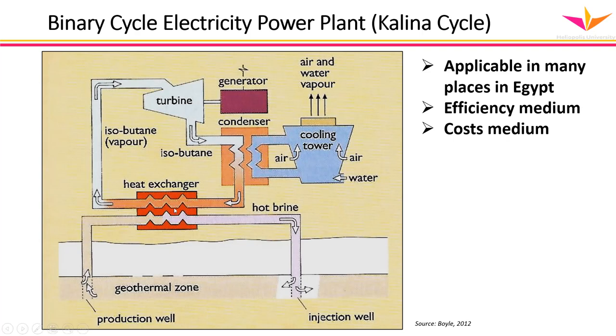Here is another picture of it. Hot water comes out, heat exchanger here in red, it boils the isobutane in this case, and that makes isobutane vapor. It drives the turbine, drives the generator, which makes electricity. The butane cools by the condenser, and then you bring it back to the heat exchanger in a full cycle to make isobutane vapor again. So you have a water cycle and an organic liquid cycle, and that is why they call it a dual cycle - it's a Kalina-like system.